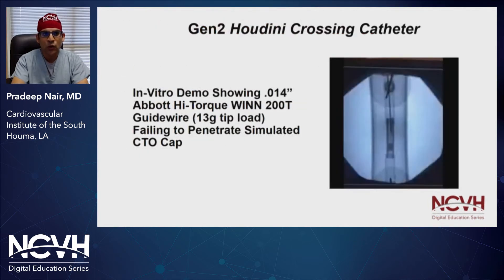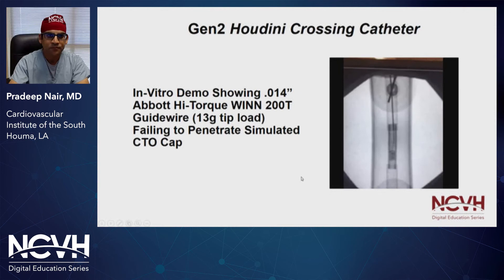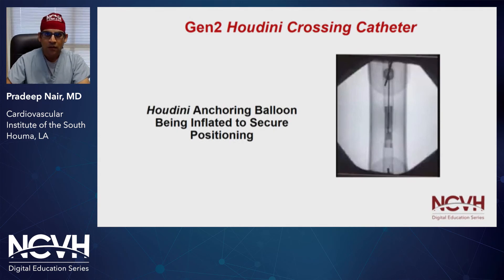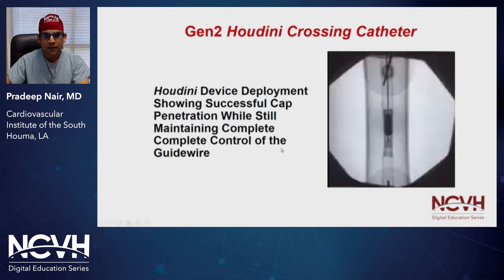Here is a video showing a 0.014 high torque WINN wire with a 13 gram tip load failing to penetrate a simulated CTO cap. This is a bench model, and you can see that standard attempts at trying to cross CTOs can be rather challenging. In the next slide, we're going to show you the next generation device on a benchtop model — where the anchoring balloon is securing the device in place, you can see the balloon being inflated. In the next video, you can see the penetration force that can be elicited to break significant proximal caps or calcific caps to cross lesions.